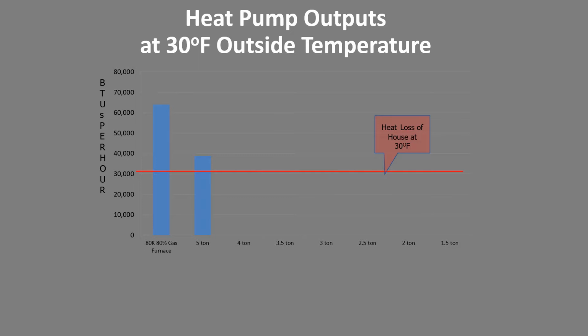We see that the 5-ton gives you almost 40K. The heat loss is around 30K, so we could say that's oversized. The 4-ton gives you a nice fit. The 3.5-ton hits it perfectly. The 3-ton starts to fall short, 2.5, 2, and then just a little bit ridiculous, the 1.5 tons. So this is one way to think of balance point. You're just basically seeing what the heat loss is at 30 degrees, and then double checking what the capacity of the equipment is at 30 degrees and trying to get as close to each other as possible.